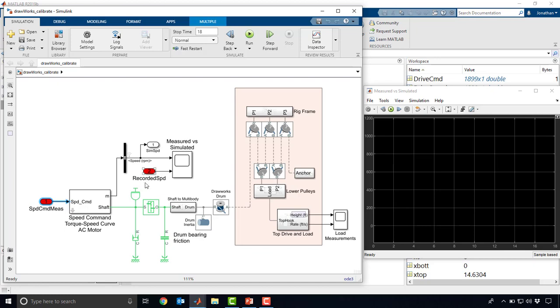Then I'm going to see the recorded speed, compare the recorded speed, what we measured in the field versus the simulated speed. If we see a good close correlation between those two, then we know our model and our parameters are pretty good and they match what we're seeing in the field. If there's not a good correlation, that means we might need to do some adjustments, either by modeling more or by adjusting the parameters so our simulation matches.